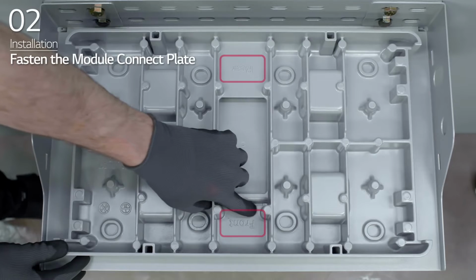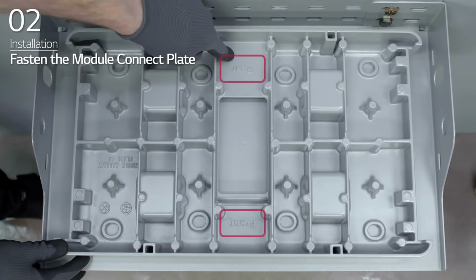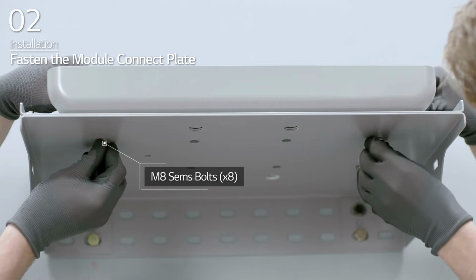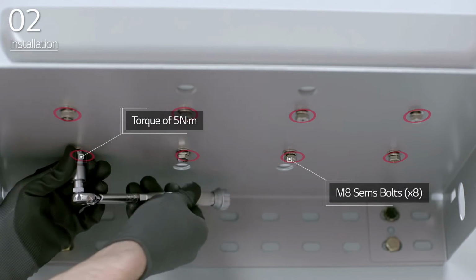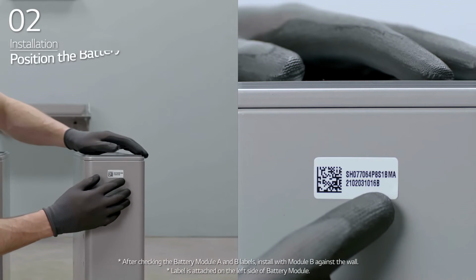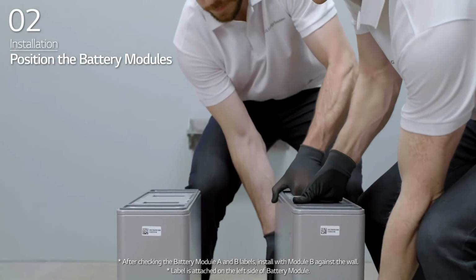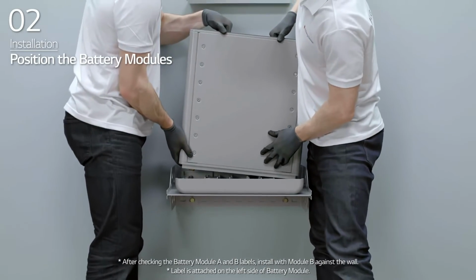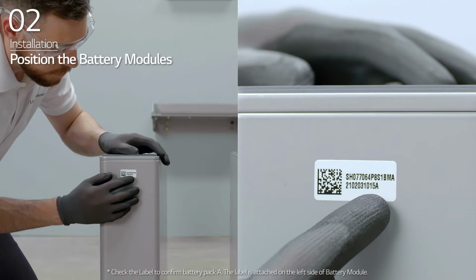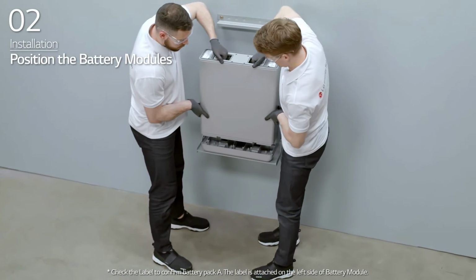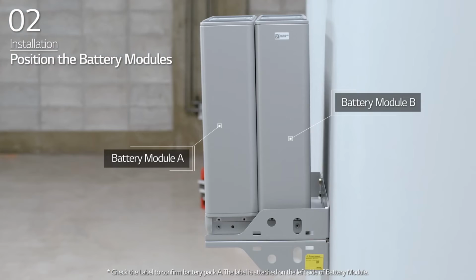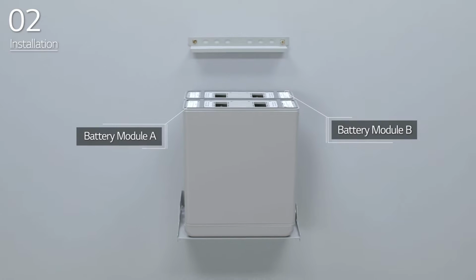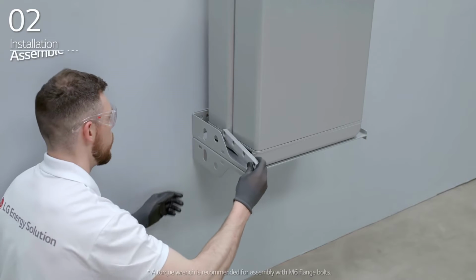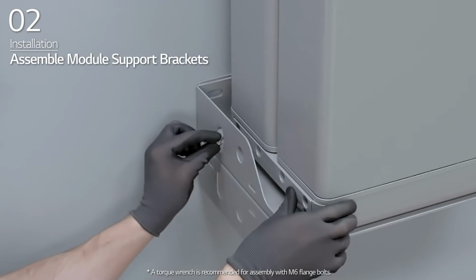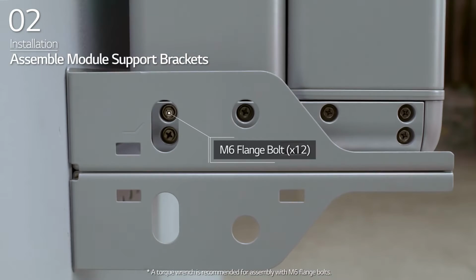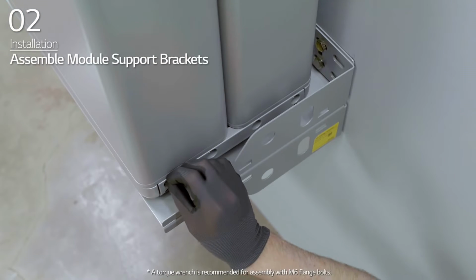Fasten the module connect plate to the wall mounting bracket using 8 M8 SEMS bolts. Position battery module B at the back of the module connect plate. Then position battery module A with the backside facing battery B. Attach the module support brackets and tighten them using 12 M6 flange bolts with a torque of 5 Newton meters.